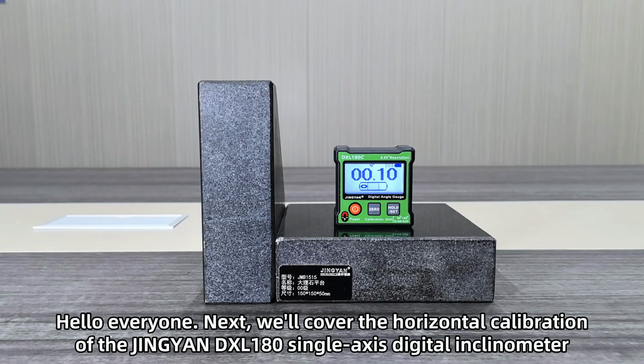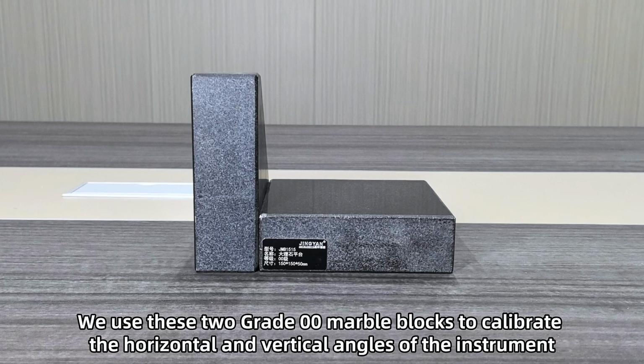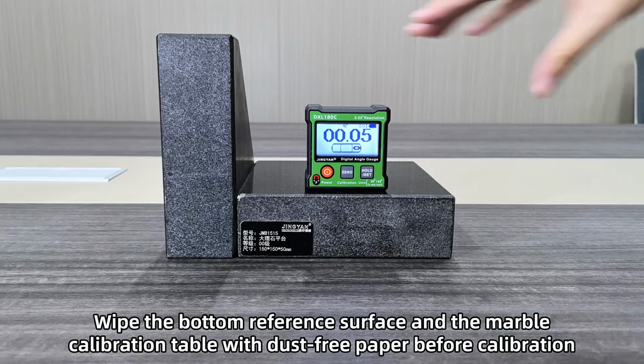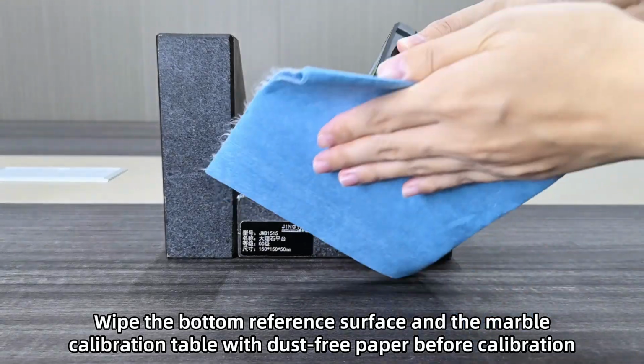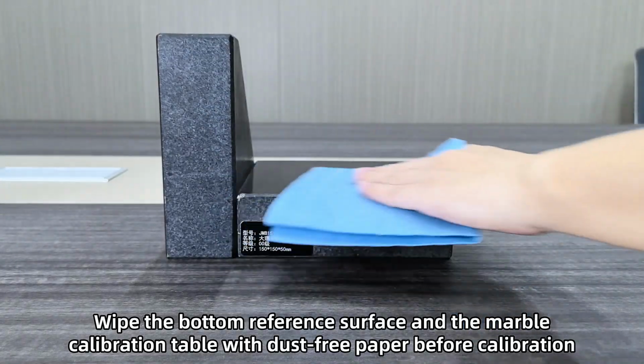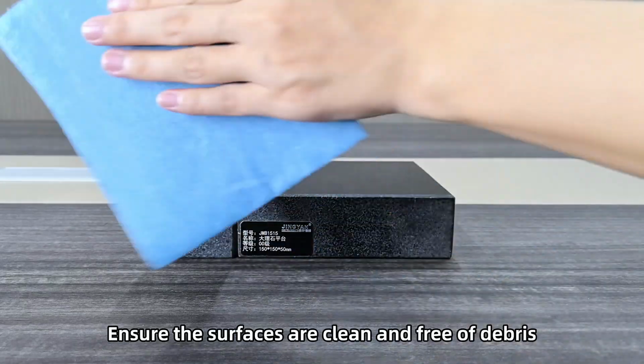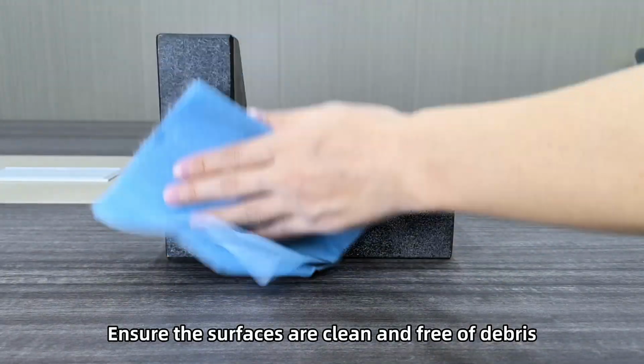Hello everyone! Next we'll cover the horizontal calibration of the JINGYAN DXL180 single-axis digital inclinometer. We use these two grade 00 marble blocks to calibrate the horizontal and vertical angles of the instrument. Wipe the bottom reference surface and the marble calibration table with dust-free paper before calibration. Ensure the surfaces are clean and free of debris.